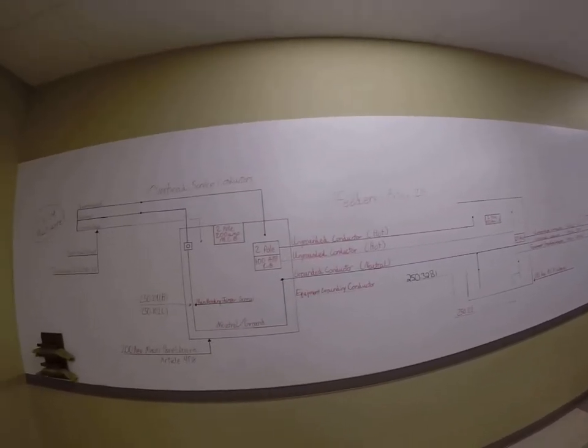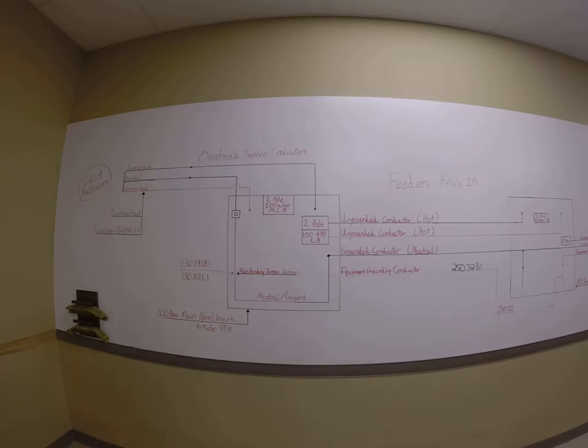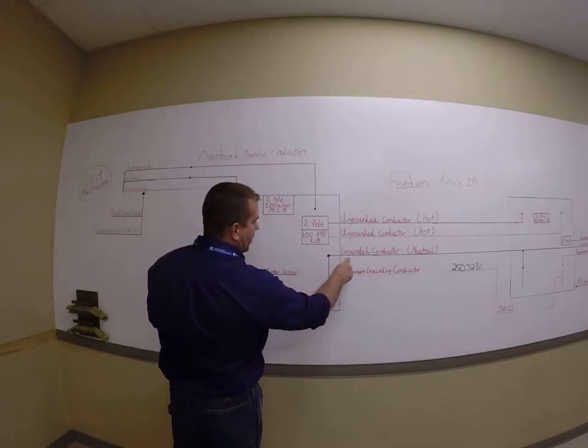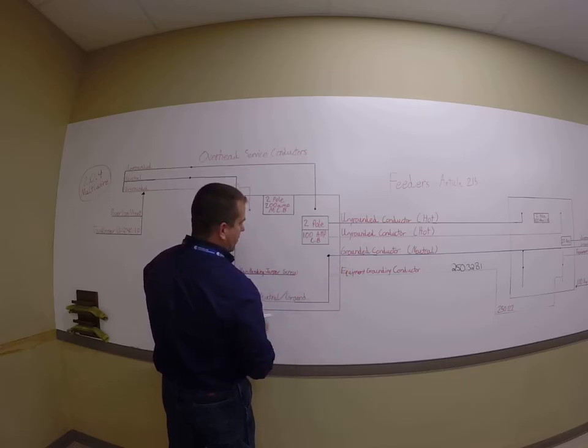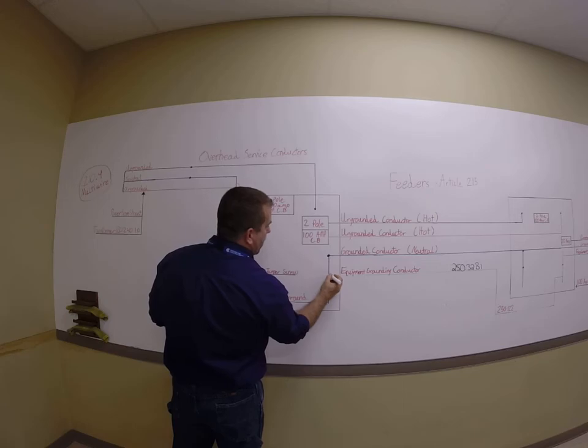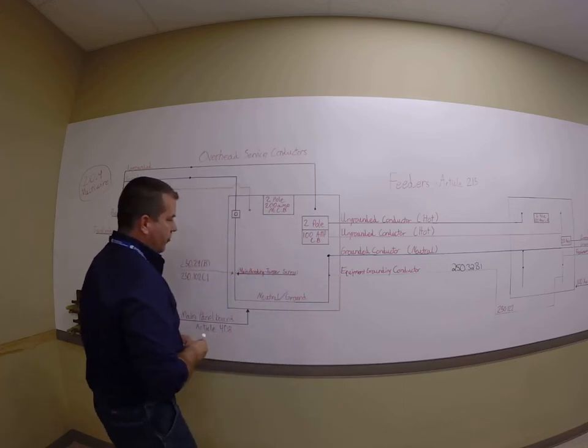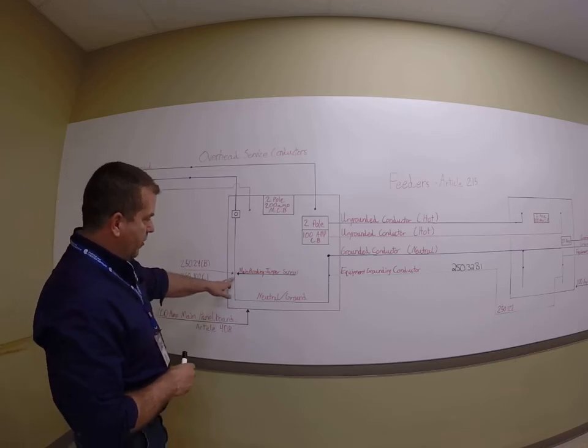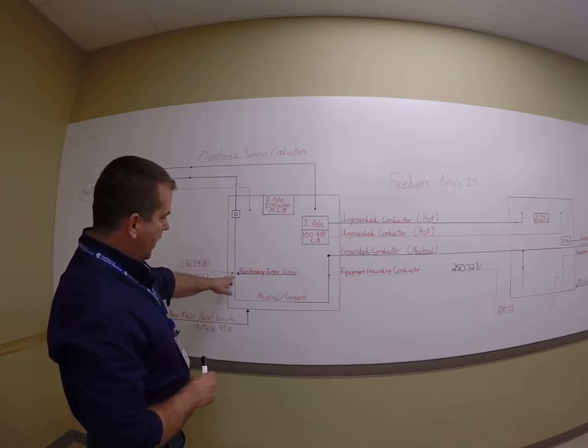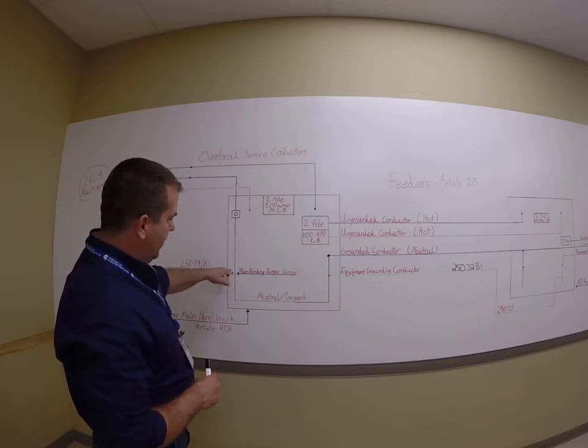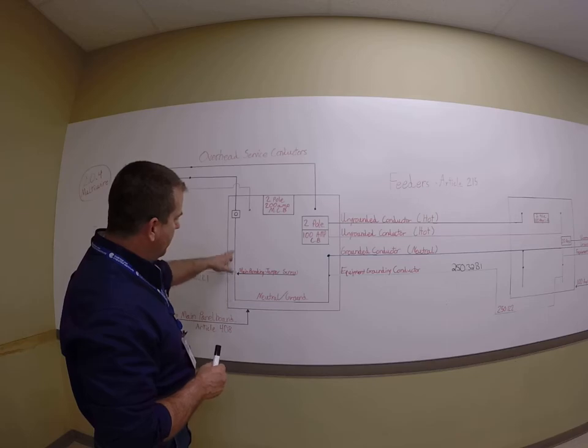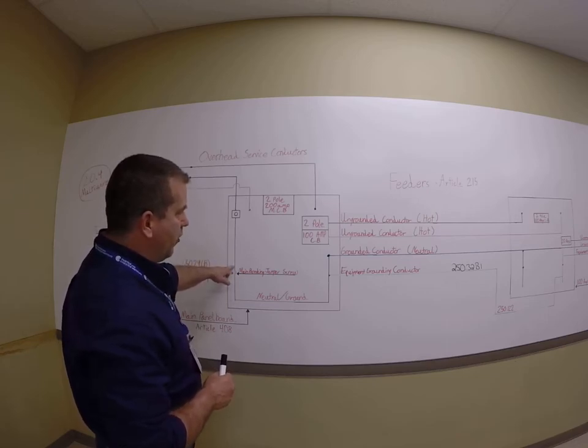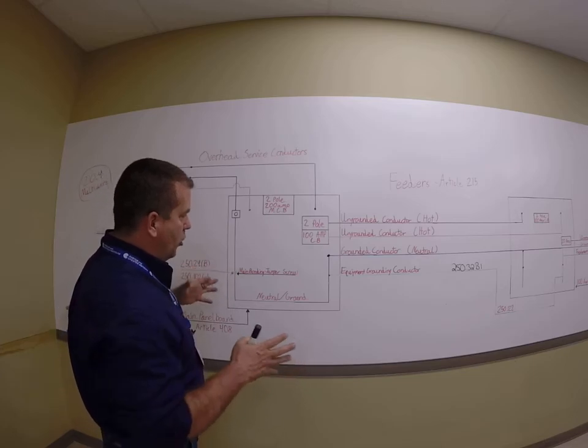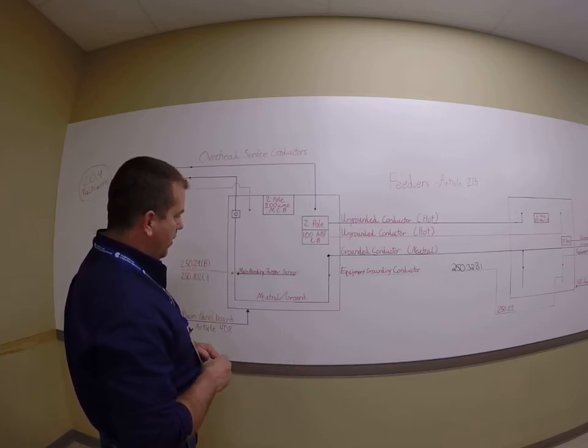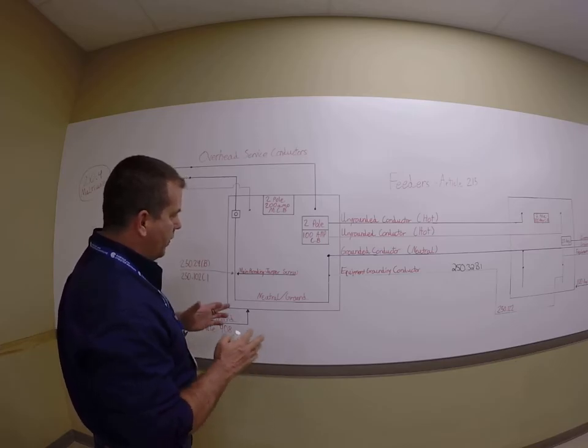But if we went back over to this panel, you'll notice that the grounded circuit conductor and the equipment grounding conductor, and of course any other equipment grounds, are actually connected to the neutral ground bar. And in that panel, you usually receive a green screw, and that green screw would go through the bus, and then it would screw into the metal busing and then into the back of the panel board can, hence bonding all your equipment grounds and your grounded circuit conductor neutrals all to the same point.